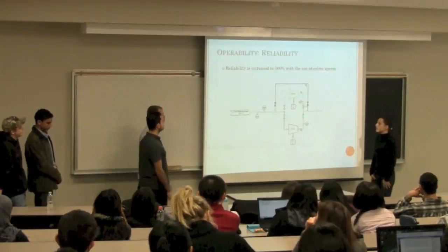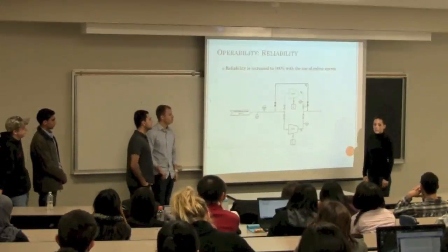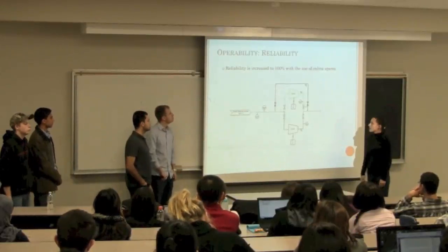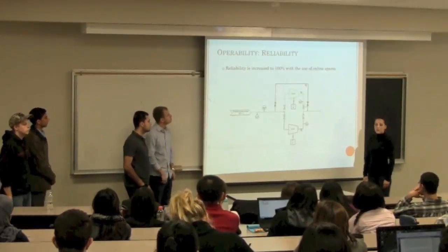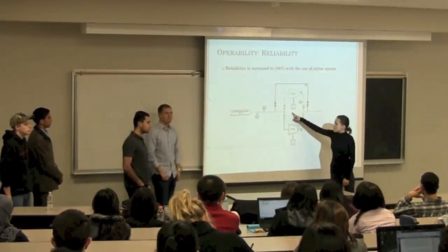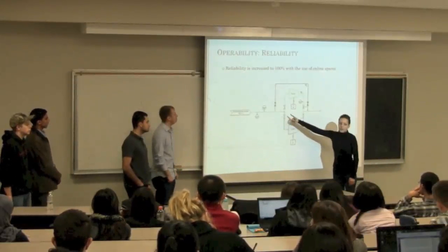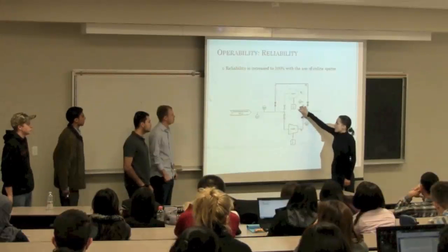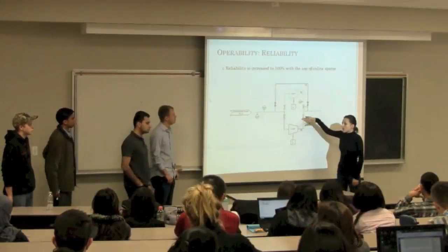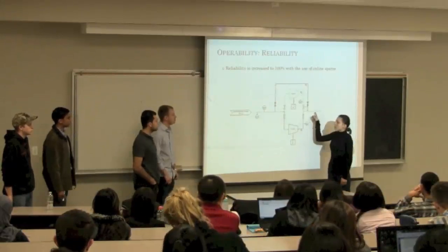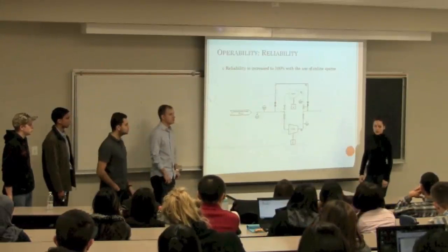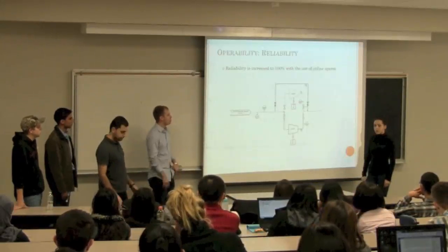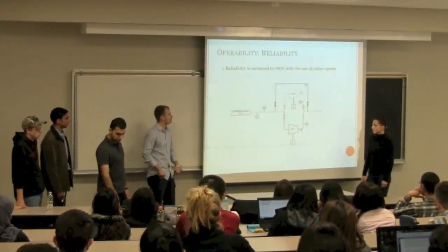Okay, so we've also introduced some features which will increase the reliability, and those are not too far away from what we've discussed in class. How we've done this is we've introduced online spares. As in this example where we're pumping ethylene, which is a gas at room temperature, there are two compressors in parallel, so if one is down, not working on the instruments, we can move to the second one, and that's seen all throughout the P&ID that is created. It can also work them in cycles, doing preventative maintenance on one while the other runs.